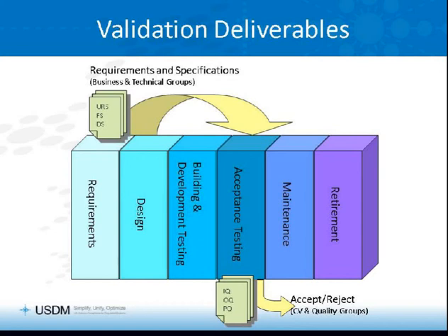You're cranking out user requirement specifications, that's what the URS stands for, functional specifications, possibly design specifications, possibly other documents as well, during the requirements and design phases. These will feed into the creation of what we're still calling the IQOQ and PQ formal acceptance tests that will be executed during acceptance testing.